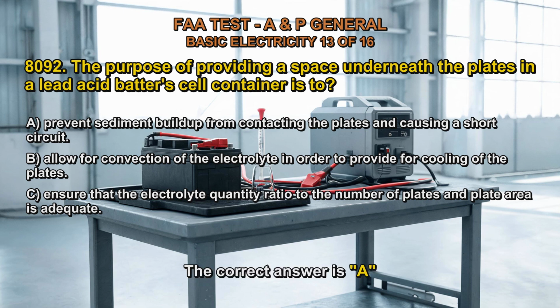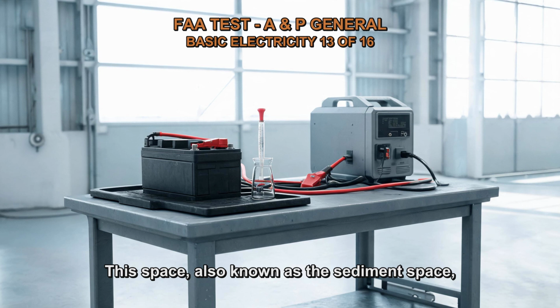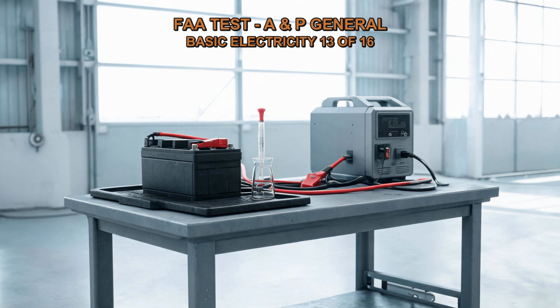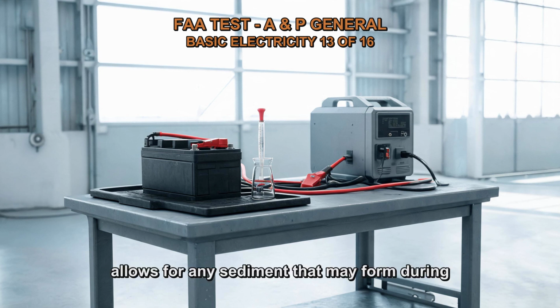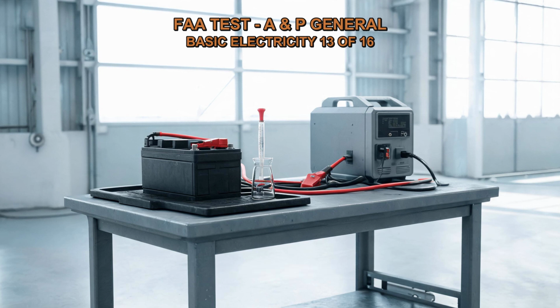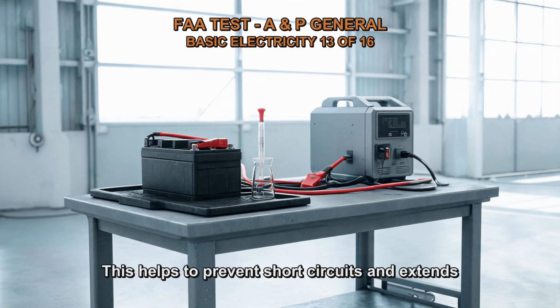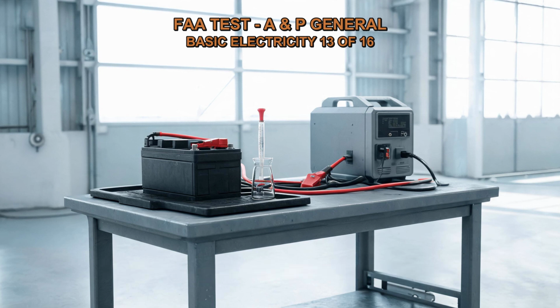The correct answer is A. This space, also known as the sediment space, allows for any sediment that may form during battery operation to settle and be safely away from the plates. This helps to prevent short circuits and extends the life of the battery.